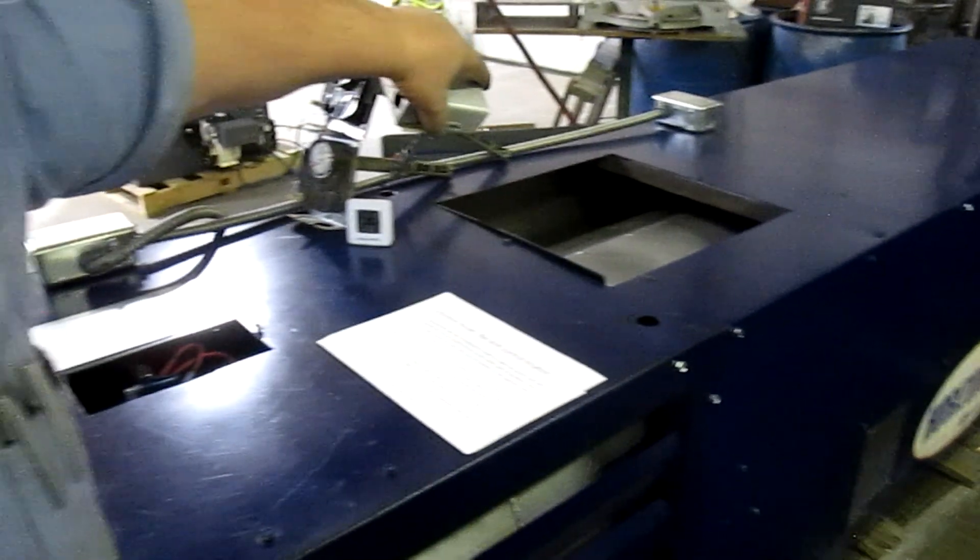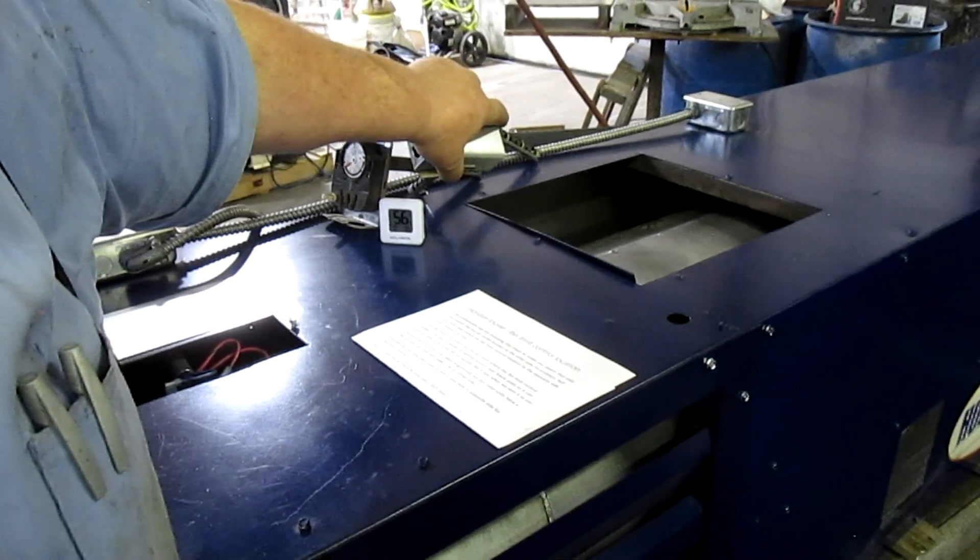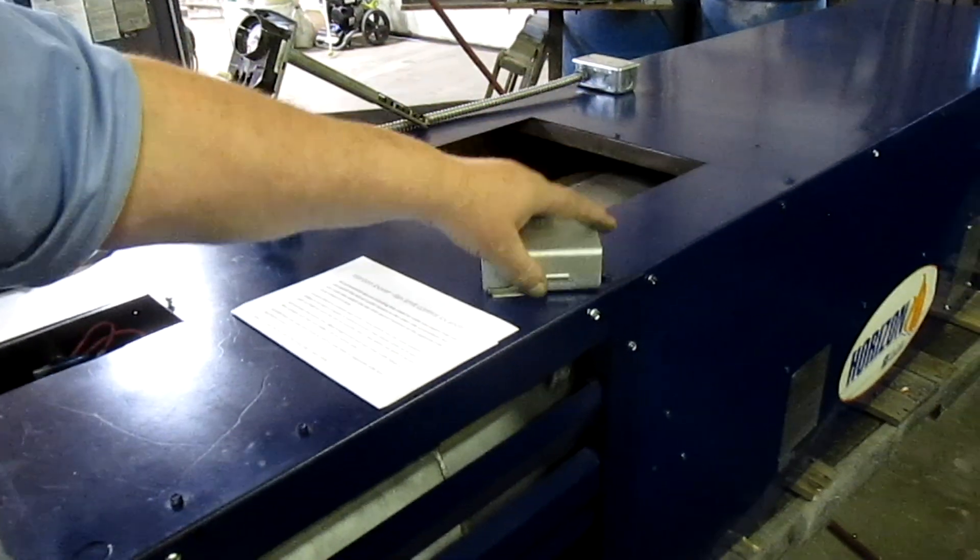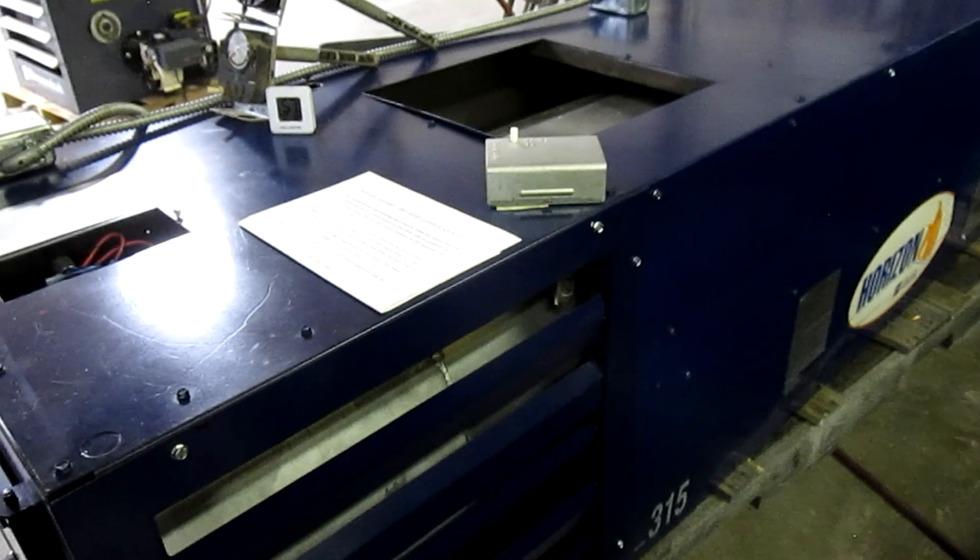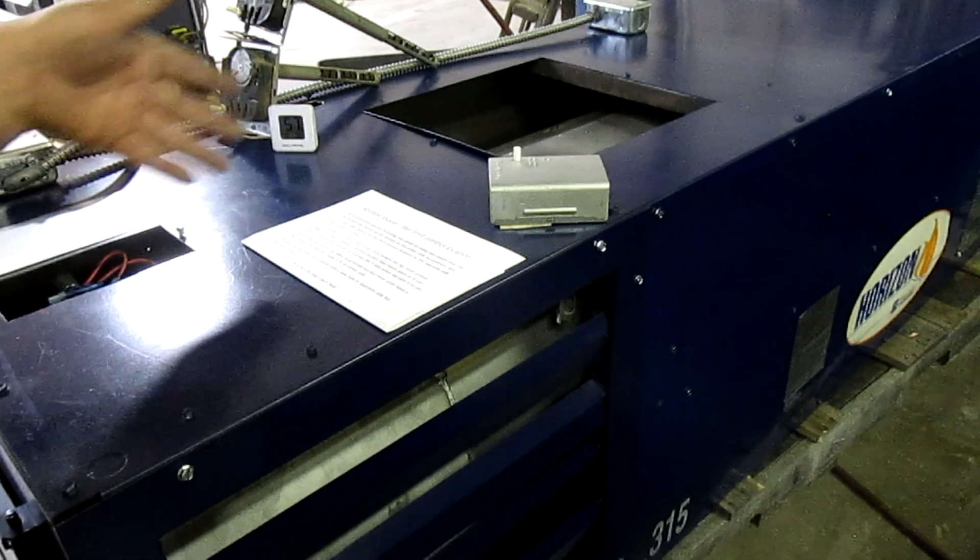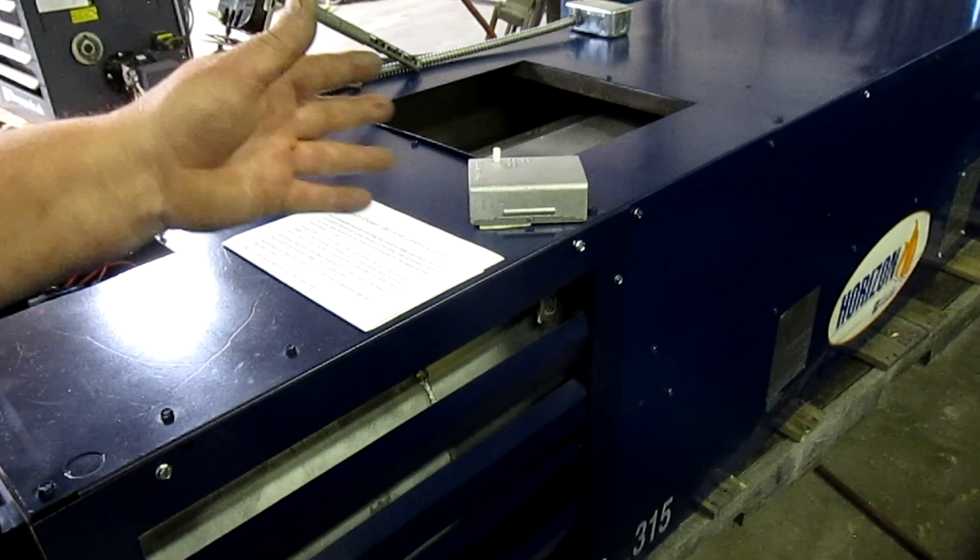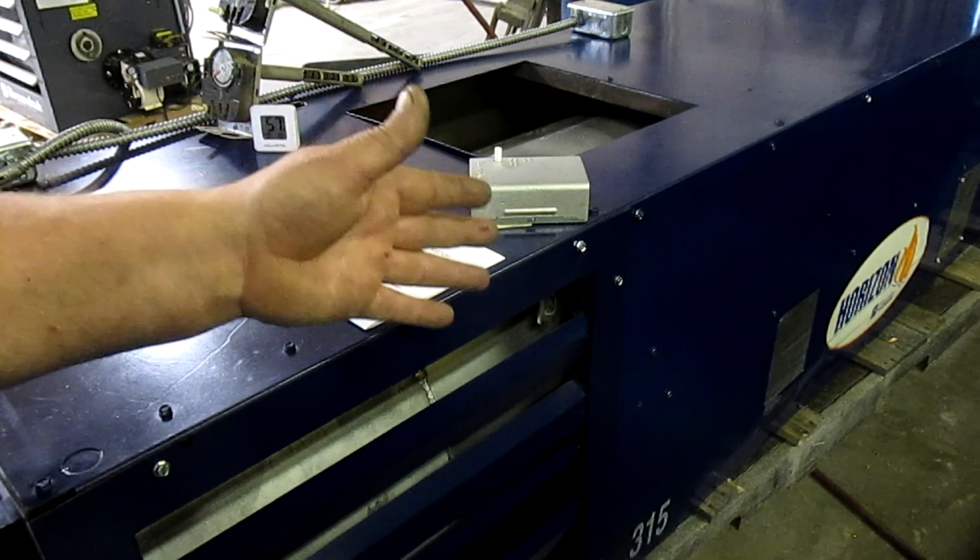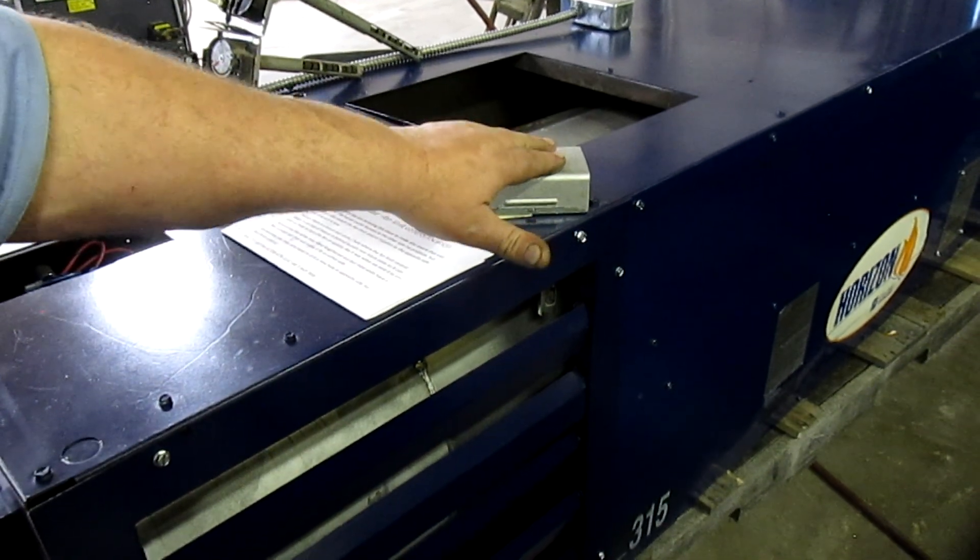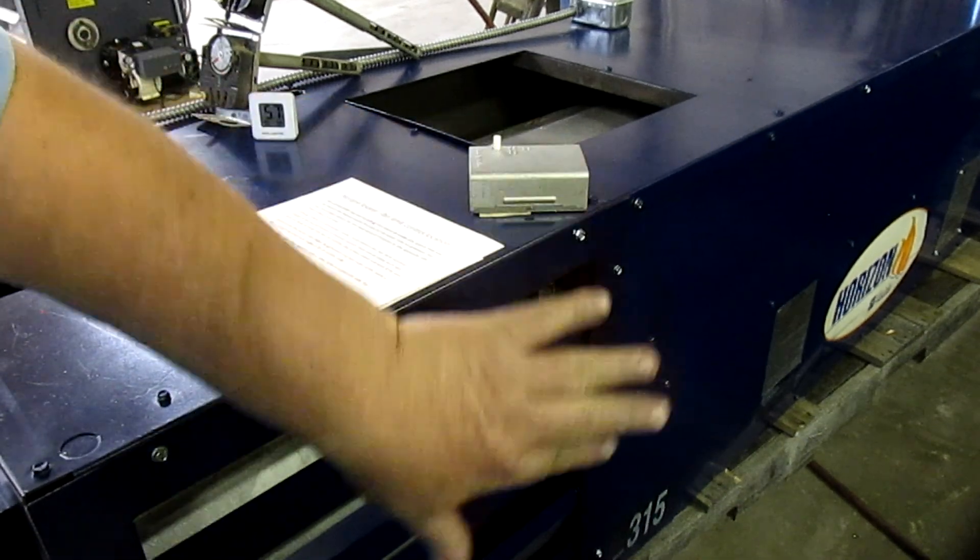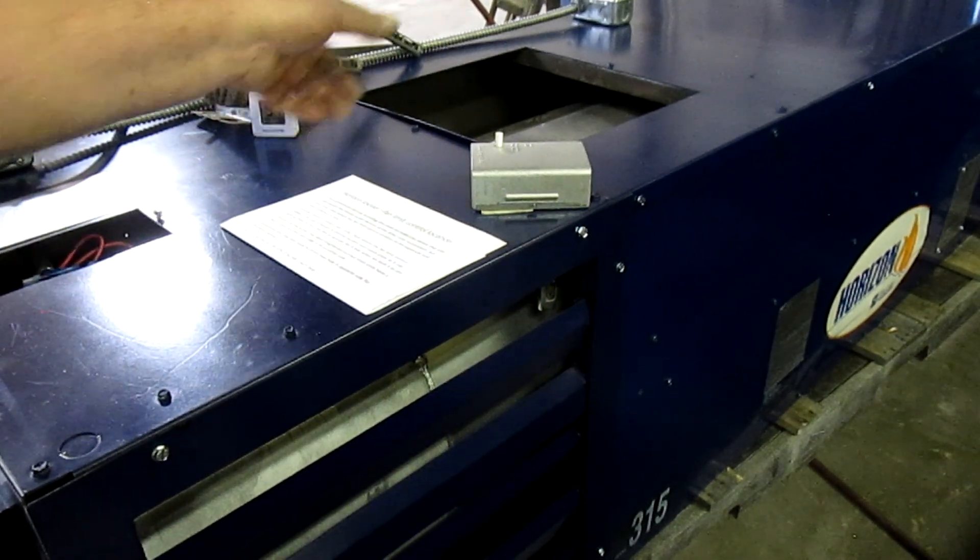This should always be on the side that has the blank plate. And with the horizon, you cannot use louvers on both sides. These switches will not work properly any way you do it. You have to put louvers just on one side. So you put the fan limit control on the side that's got the blank plate on, which will be the back on this unit here.